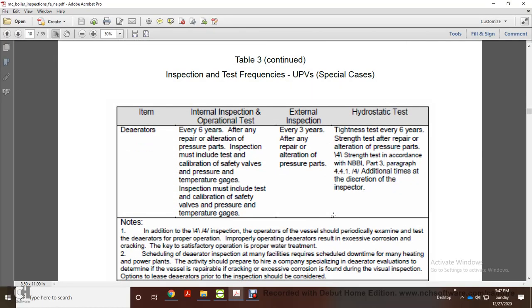Alright, your inspection frequencies: UPV, deaerators every 3 years. After any repair, alteration, pressure parts, inspection must include tests of calibration, safety valves, pressure, temperature gauges. External inspection after 3 years, every 3 years after repair, alteration, pressure parts.